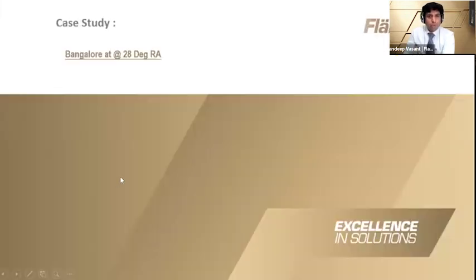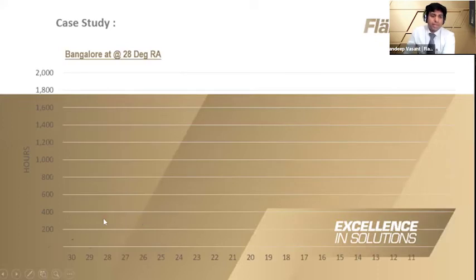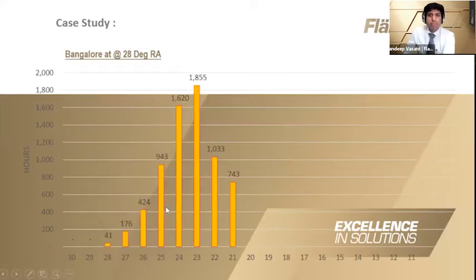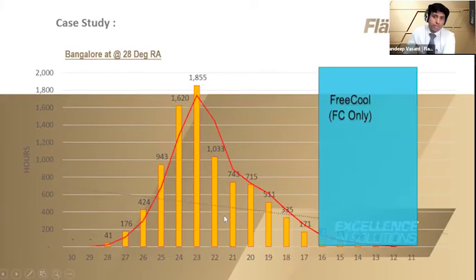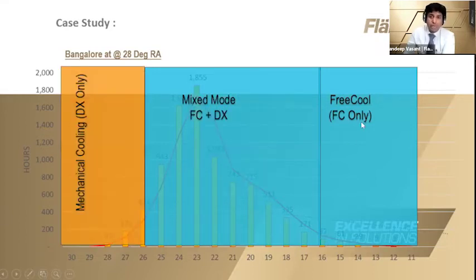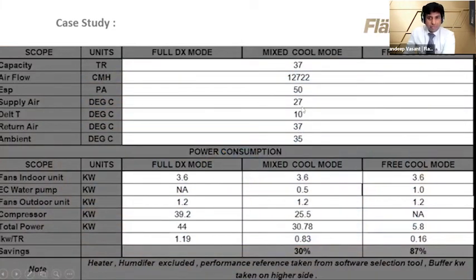So to pull back, thanks to the ISHRAE 8760 hours data which I got, I have plotted the graph of the different ambients in Bangalore vis-a-vis the operating temperature in the same indirect free cooling unit. If you see, at a certain ambient, free cooling can be used for so much of the time, and then it goes into the mixed mode, and then we are restricting the usage of the direct expansion. So you get a saving here because your direct expansion comes into picture at a very limited time. So that's on the indirect free cooling.